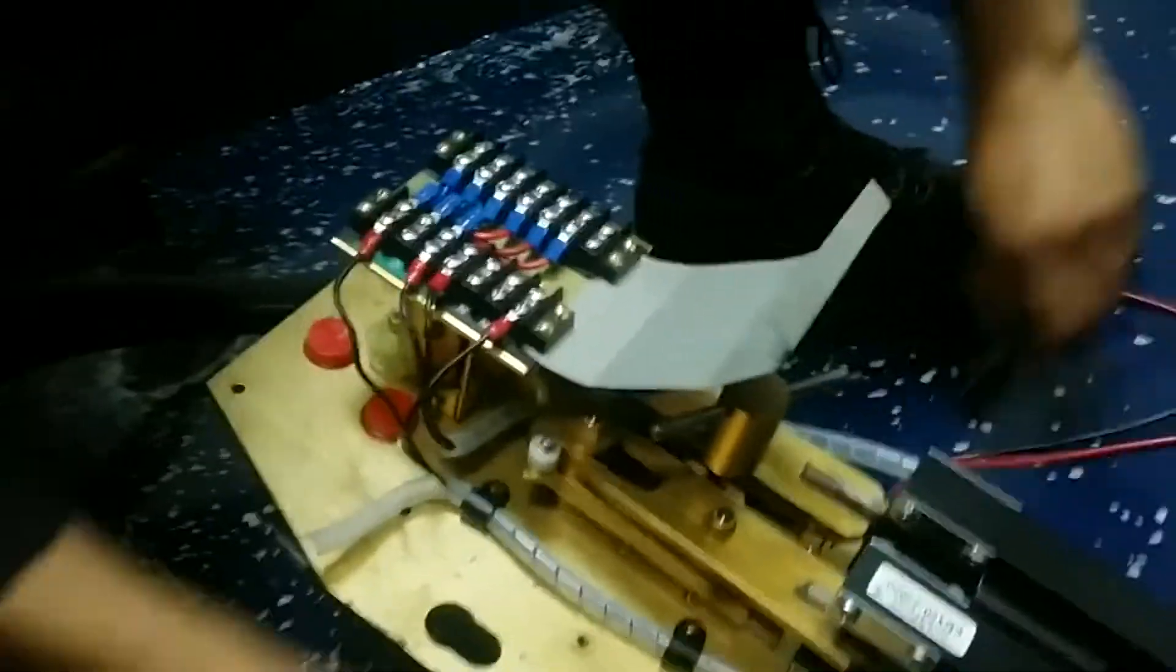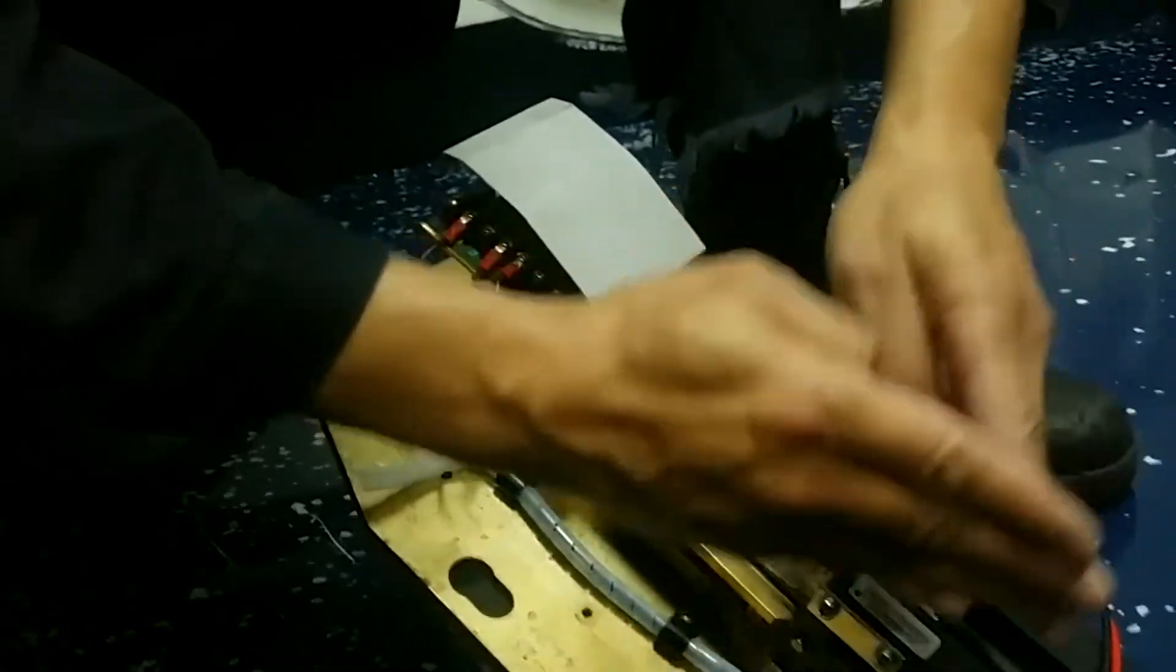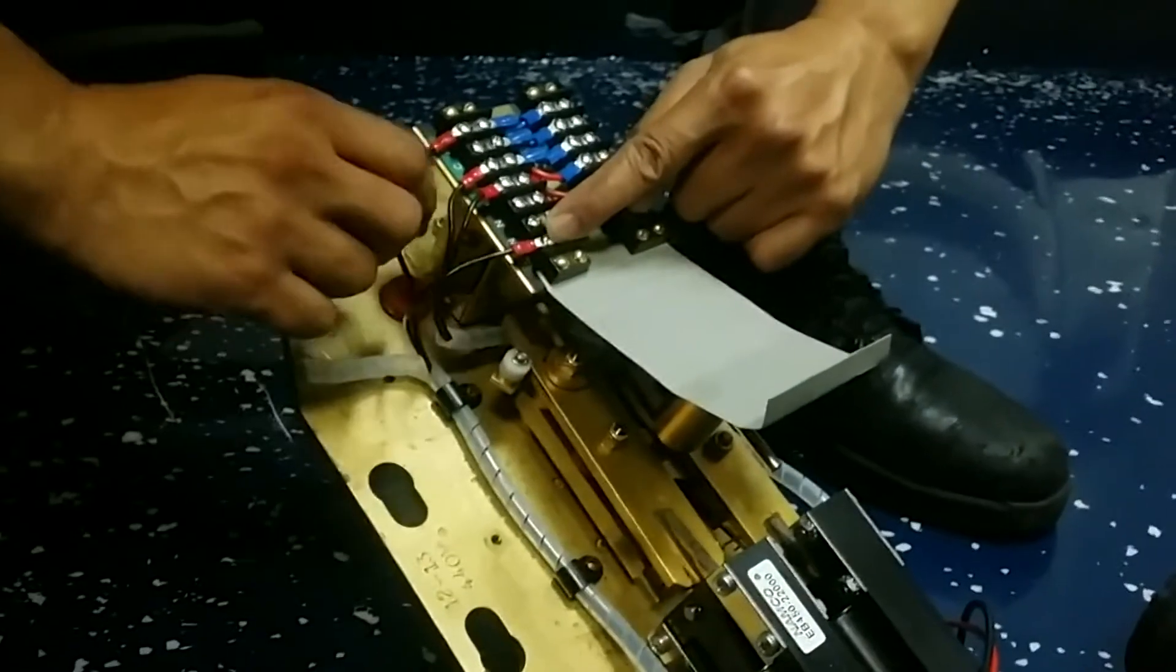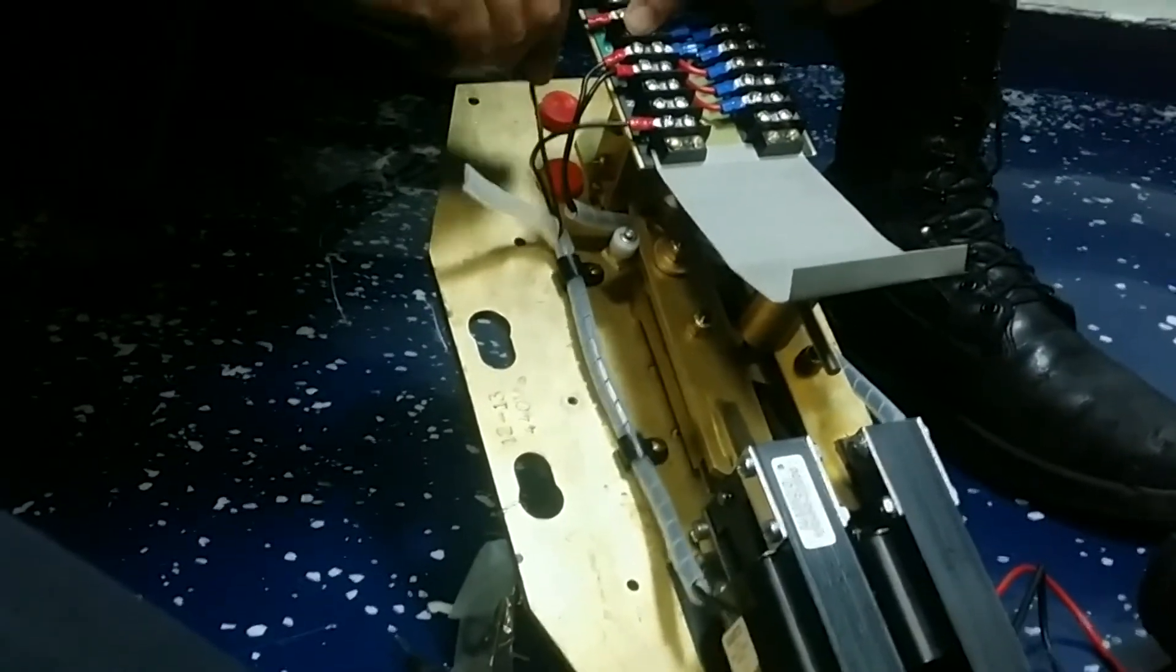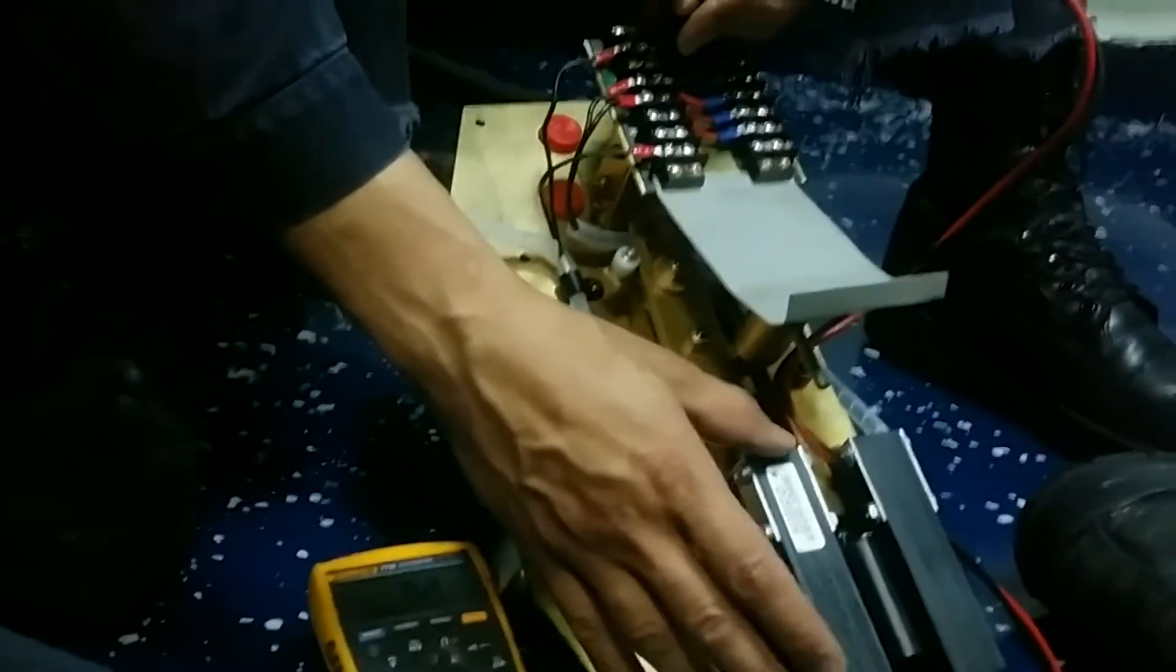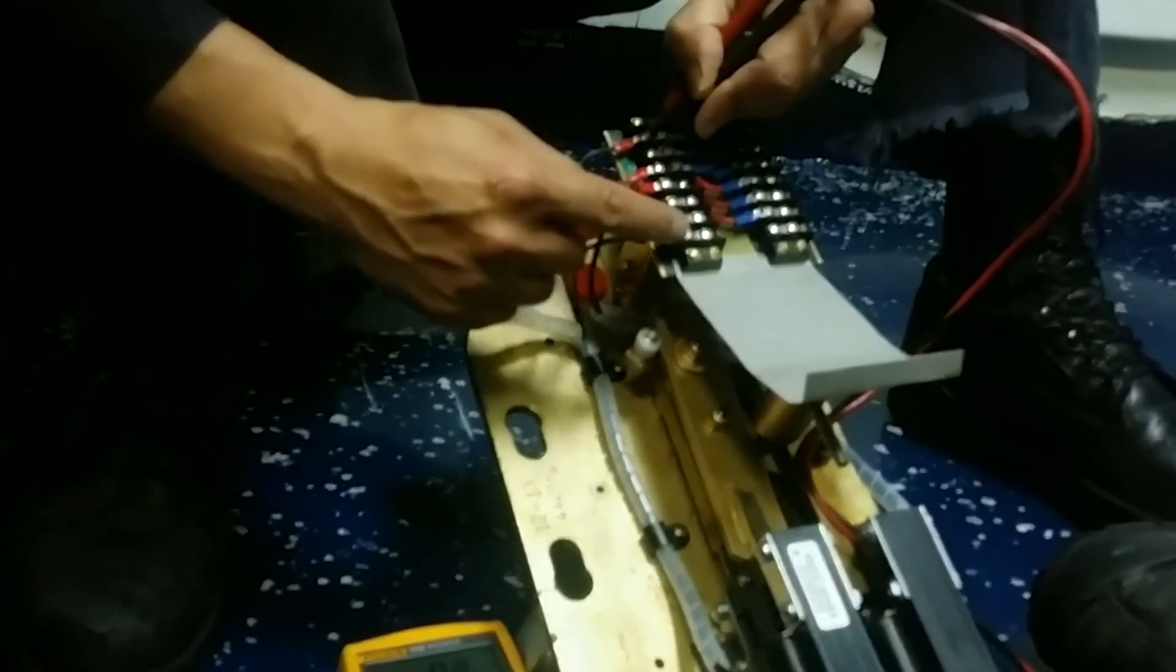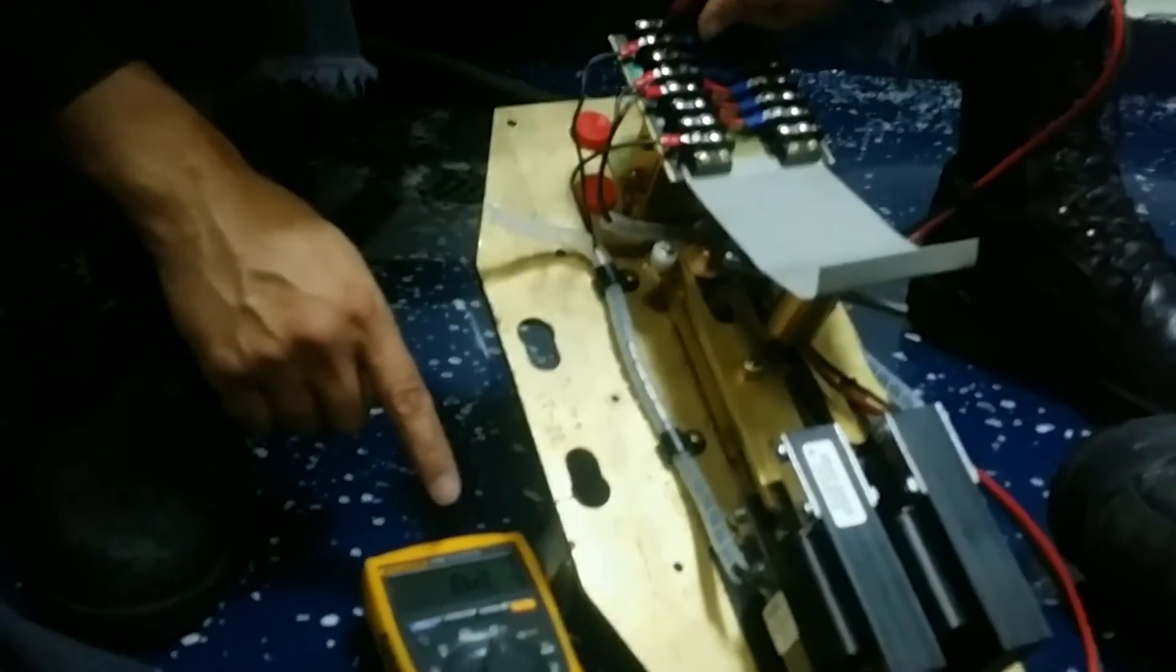This side is wired in a way that, if you pay attention, right now the valve is closed, so what we need is for the valve to open. This is my open solenoid, so we got to give priority to this open solenoid. The push button for open is going to be wired into this one, so whenever they press the push button to open, this one will get energized, the valve will shift, but this wire has to be energized. The common wire will be connected here, and we need this wire to be shorted with the common wire. Let's see, we put the multimeter, and we see a short there. This valve is the one that we want to energize, so therefore that's the one with continuity. There will be one phase of power here, having this one ready to be energized, only waiting for the open push button signal to come in. Once the open push button comes in, the valve will quickly shift.